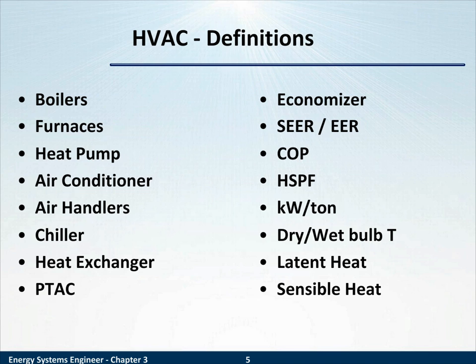The dry bulb, the wet bulb temperature. Dry bulb is just what you might consider the regular air temperature. Wet bulb, the technical definition of the way of measuring it, is as if you had a wet sock around your thermometer and you spun it around to cool that wet sock through evaporation. The temperature inside would be a wet bulb temperature. Wet bulb takes into account humidity and evaporation.